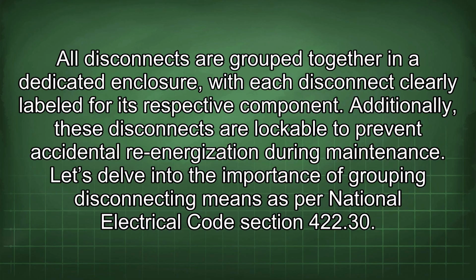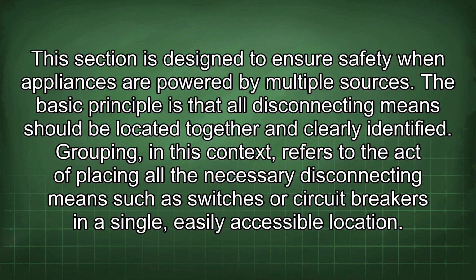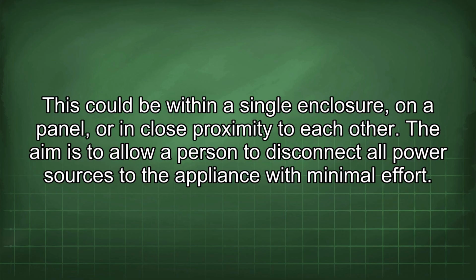Let's delve into the importance of grouping disconnecting means as per National Electrical Code Section 422.30. This section is designed to ensure safety when appliances are powered by multiple sources. The basic principle is that all disconnecting means should be located together and clearly identified. Grouping, in this context, refers to the act of placing all the necessary disconnecting means such as switches or circuit breakers in a single, easily accessible location. This could be within a single enclosure, on a panel, or in close proximity to each other.